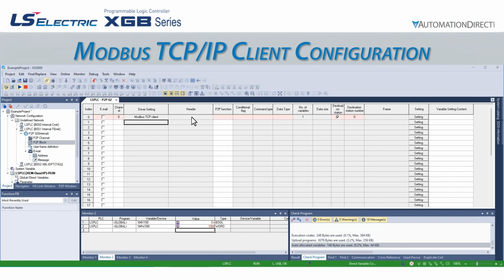We leave header blank, and then select whether this will be a Modbus read or a Modbus write. Let's start with a read function to read the current drive speed. For the conditional flag column, we can select any Boolean direct or flag variable. We will use the system flag _T200ms. This will cause the PLC to send every 200 milliseconds. If we wanted to use a program-determined message send rate, we could use a %mx memory location and then control that address with our logic.